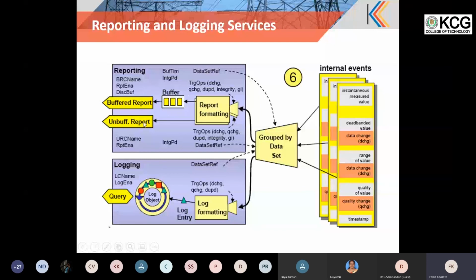In the buffered scenario, this is getting into SOE, it is sent out on a faster basis, but when there is a communication break, there is a buffer, this is getting buffered, and when communication is re-established, all the snapshots containing any of the triggers that caused the report to generate will be sent out in the buffered report.